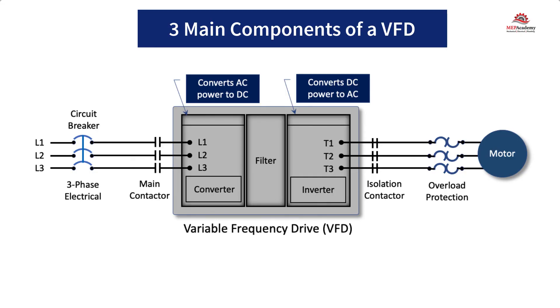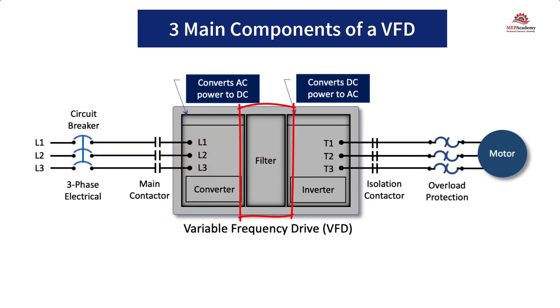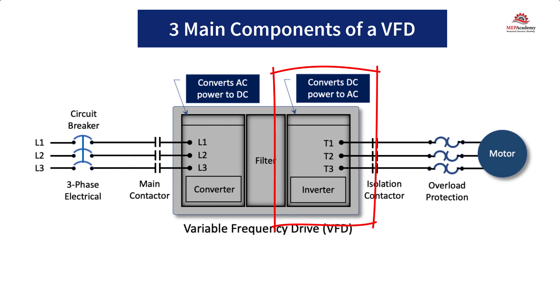The three main components of a VFD convert AC voltage to DC voltage and then back again using a simulated AC voltage. First, you have the converter or rectifier, which takes the incoming three-phase alternating current AC power and converts it into direct current DC power. Then the filter smooths it out and rectifies the DC voltage. Finally, the inverter rapidly switches the direct current DC voltage on and off to create a pulsating voltage that mimics AC voltage. By controlling the rate of switching, the frequency can simulate AC power applied to the motor to control its speed — essentially switching from DC back to AC.